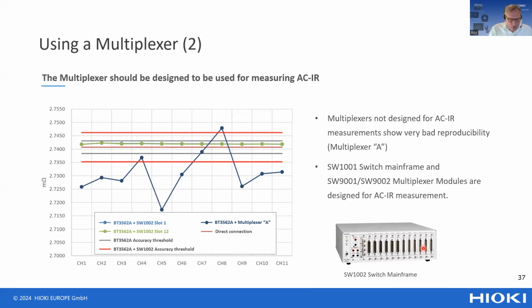Our engineers in Japan also tested a multiplexer not suited for AC/IR measurements, shown as the blue trace. The green trace is as flat as the Netherlands, but the blue trace shows hills and mountains like the Alps. Therefore, an off-the-shelf multiplexer will not give you good repeatability. You need a multiplexer really designed for AC/IR measurements.